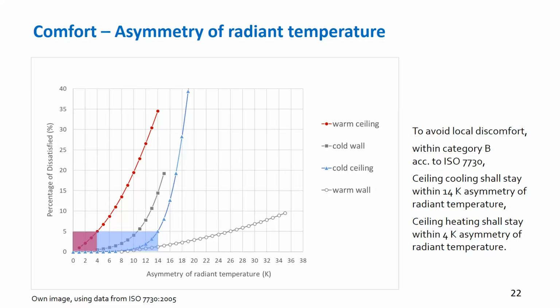And if you go for a cold ceiling, we are very much indifferent or happy with a cold ceiling. We could allow, according to ISO 7730, asymmetry of radiant temperature of even 14 degrees to enter a level of 5% of dissatisfied people. So we're very much sensitive against heat from above, very much less sensitive from coolness from above. And sometimes I'm confronted with the question, but hey, are you crazy? The sun is hot and it's above me. And I say, yes, that's true, but the sun is so small and the big sky is very cold. So we're trained to the cold skies above our head, and the cold skies give us evolutionary training for it's nice to have coolness above and not warm above.